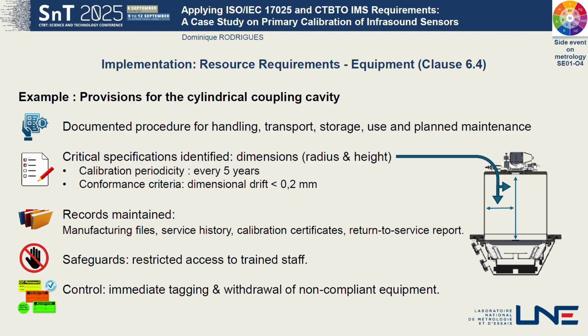So then we have to define two things, the conformance criteria and the periodicity for monitoring these critical specifications. The conformance criteria here is a dimensional drift, because we know by the calibration the true values, but it can drift in time. So we have to define a dimensional drift, which we define here as 0.2 millimeters, which is reported in the uncertainty budget. Then, after that, we have to define the periodicity. The periodicity is a risk assessment, I would say. It's a balance between the cost and the risk.